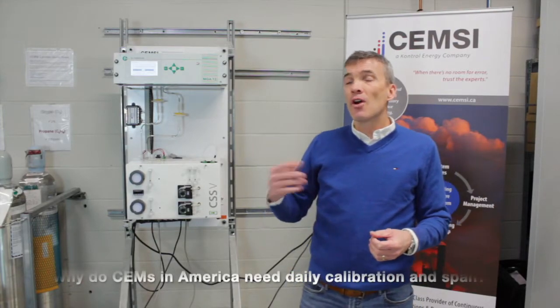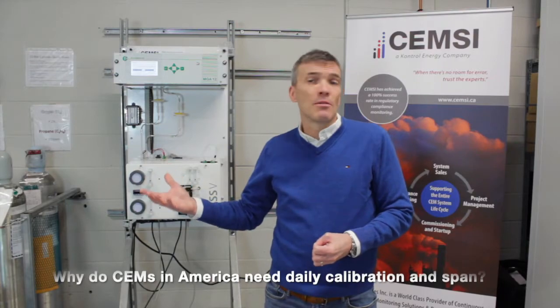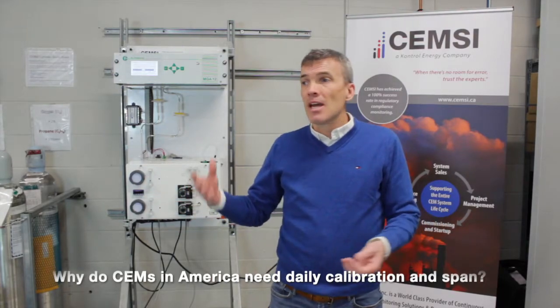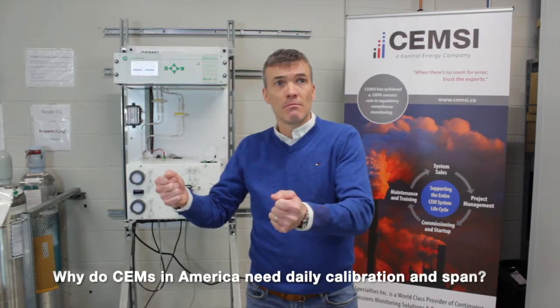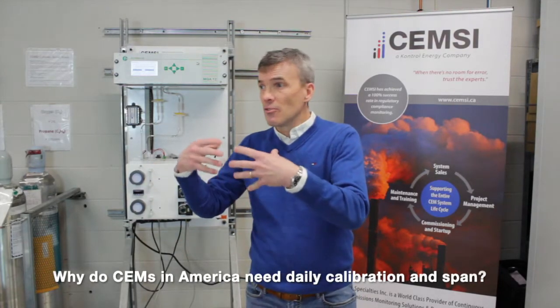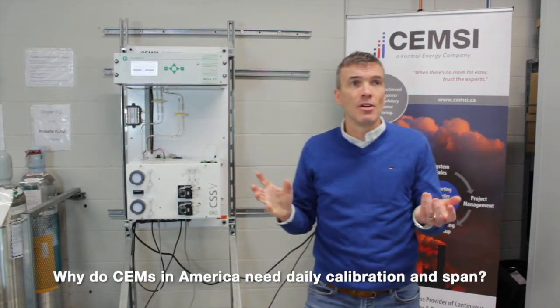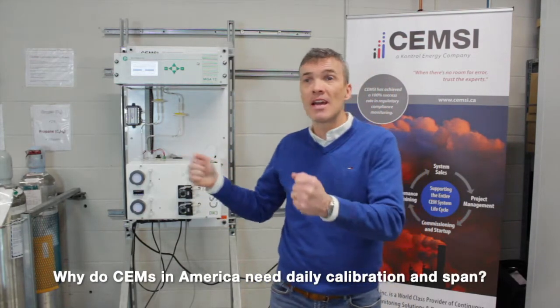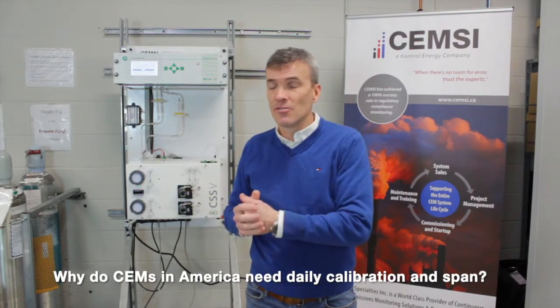But for us, whenever we deal with a lot of manufacturers in Europe, it's completely different than North America. In Europe, if you want to sell an analyzer, you have to submit it to the government. The government has to inspect it, and they put a stamp on it that it's approved. And this inspection isn't a 2-minute kind of inspection. Basically, they take the analyzer for a year. They do TUV testing in the case of Germany.